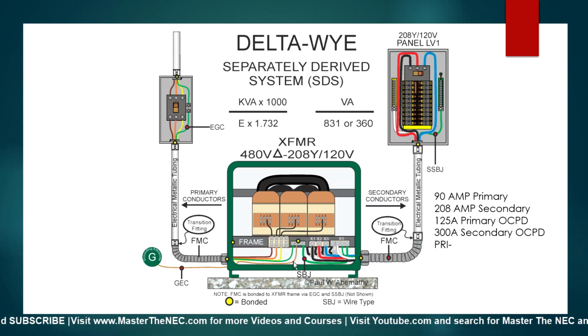Now, what about this grounding electrode conductor? Well, if it's going to a ground rod, it would be just 6 gauge copper or 4 aluminum. Of course, you have to be careful not to terminate aluminum within 18 inches of the earth. But it could be aluminum.